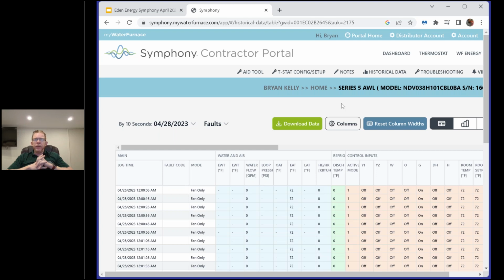If you spend the $300 to fully load your piece of equipment, you'll be doing maintenance remotely. You can see this column right here—this particular unit didn't go for the option, but you can see it. You can log in and validate every month in about 3 seconds that this 3-ton unit has great performance, and send that homeowner a report saying we've logged in, validated the performance, it meets factory spec, there are no lockouts, the unit is running great, and we'll review it again in 30 days. If you're charging $100 for that service and also plan to visit physically once a year to validate everything on site, your competitors that aren't doing that can't compete with you. It's like Elon Musk versus the lunar rover—this is the future, but it's available to you now.